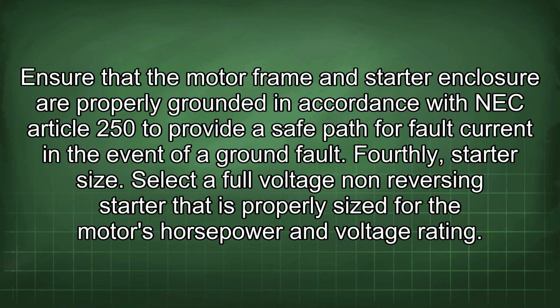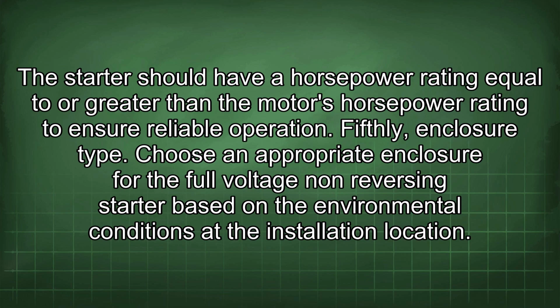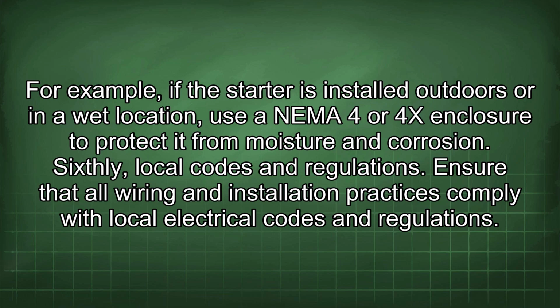Thirdly, grounding. Ensure that the motor frame and starter enclosure are properly grounded in accordance with NEC Article 250 to provide a safe path for fault current in the event of a ground fault. Fourthly, starter size. Select a full voltage non-reversing starter that is properly sized for the motor's horsepower and voltage rating. The starter should have a horsepower rating equal to or greater than the motor's horsepower rating to ensure reliable operation. Fifthly, enclosure type. Choose an appropriate enclosure for the full voltage non-reversing starter based on the environmental conditions of the installation location. For example, if the starter is installed outdoors or in a wet location, use a NEMA 4 or 4X enclosure to protect it from moisture and corrosion.